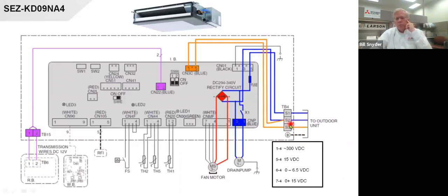Again, S2 and S3 are communicating to the outdoor unit. S1 and S2 is your line voltage. We do have a rectifying circuit in here to go to the fan motor. But what I wanted to show you here is this little box. These are your terminals 1 and 2, or 1 and 4, and here we left 2 pins off. This is 300 volts DC between 1 and 4, 4 being the negative side or common.